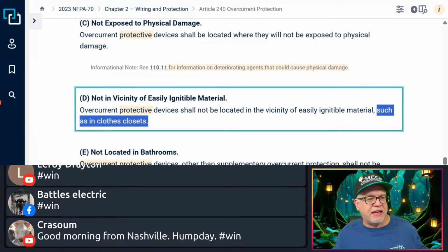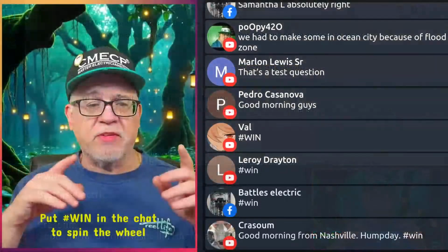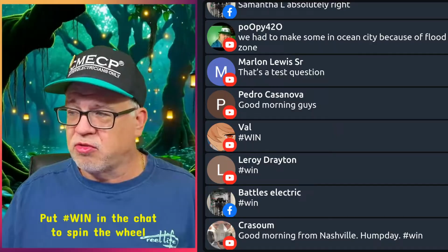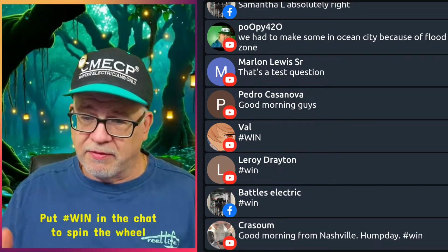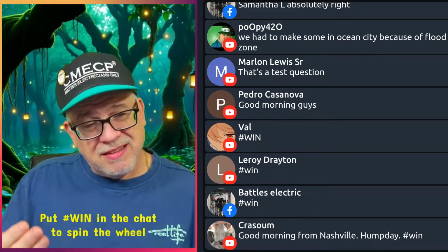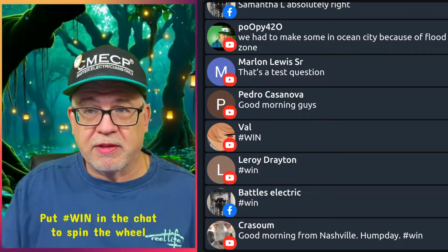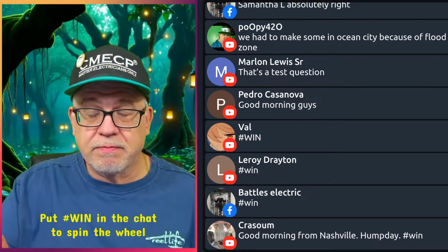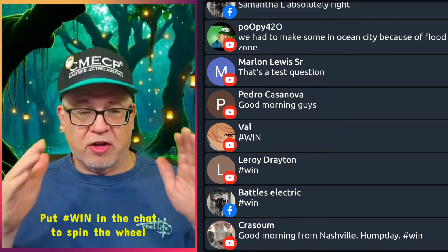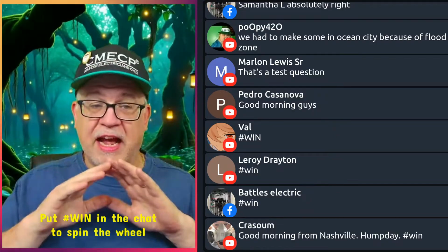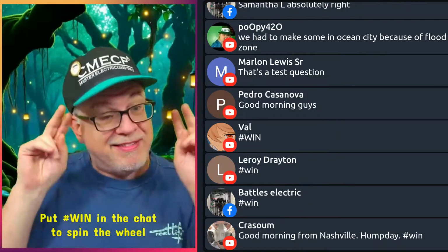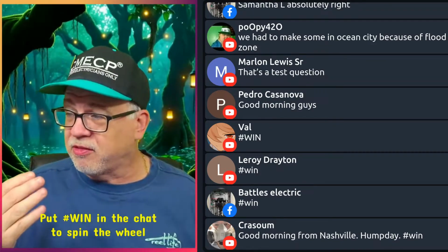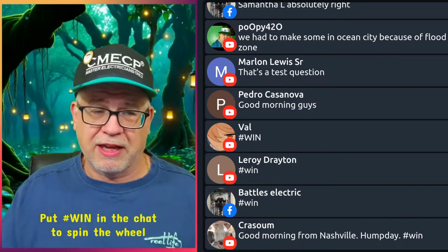So, folks, anytime you see that in the code, where something says such as, that is not an all-inclusive list. That is just giving you some food for thought. You have to have enough common sense to look at it and go, well, this is not a clothes closet where I want to put this overcurrent device, but there is easily ignitable material near it. And the answer is yes. Then you do something to section it off to remove that. I'm putting it in its own cabinet. You do whatever mental gymnastics and working with your AHJ that you have to do. It doesn't just have to be a clothes closet where this will be applicable.